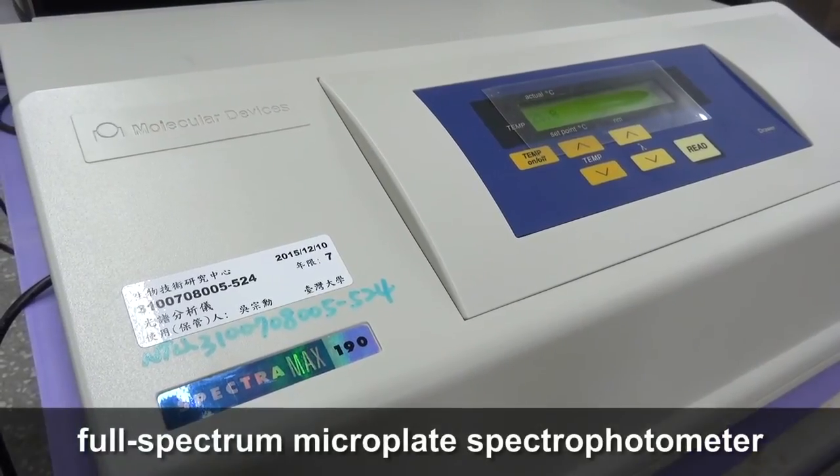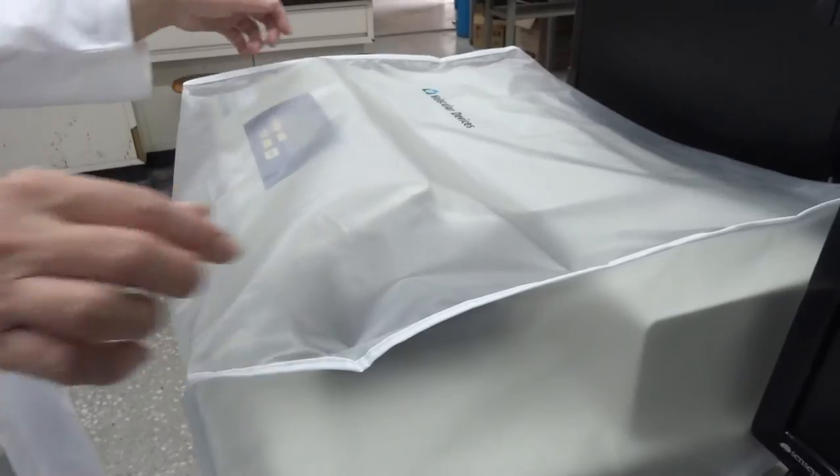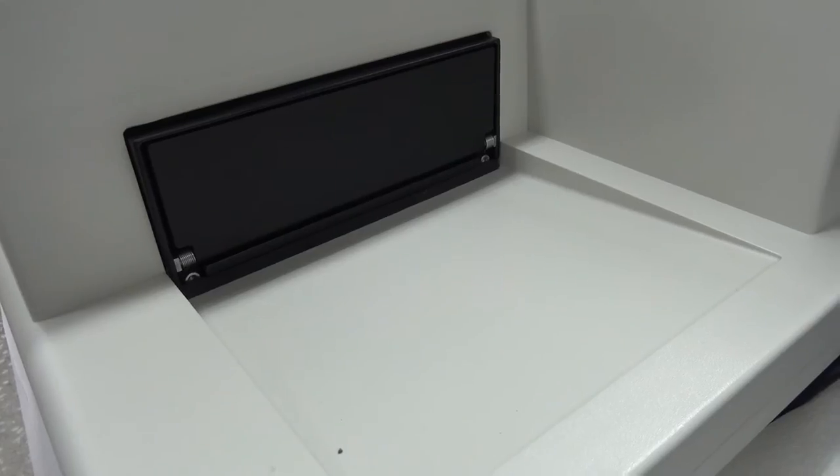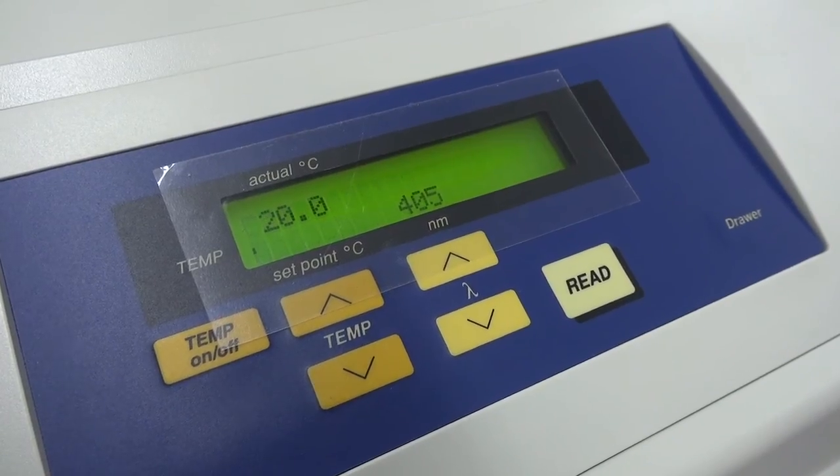B. Now we demonstrate how to operate a full-spectrum microplate spectrophotometer. 1. Remove the dust cover and turn on the machine. Wait for the microplate holder to extend out and start up to be completed.